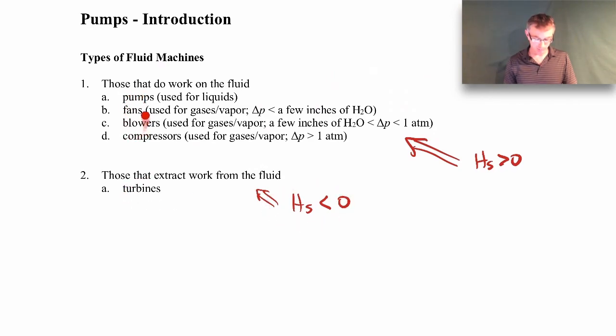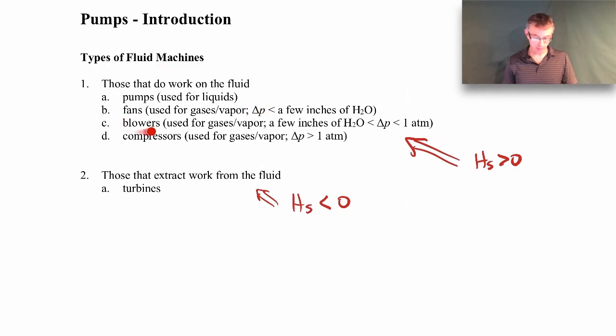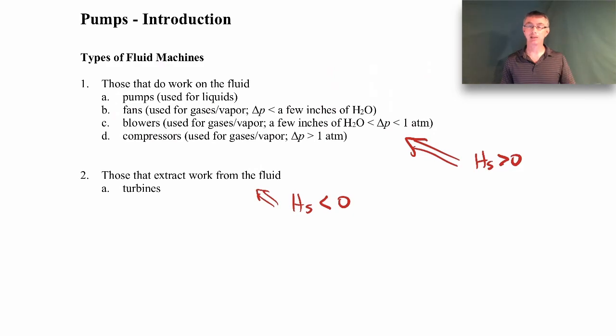There are some terminology differences between these kinds of devices. Pumps are typically used for liquids. Fans are used for gases or vapors at very low pressure changes — meaning a small pressure change across the fan. Blowers have a higher pressure change but are also used for gases and vapors. Compressors are also for gases and vapors but with a larger pressure difference. So fans, blowers, and compressors all operate on gases or vapor, differing mainly in how much pressure rise there is across the device.